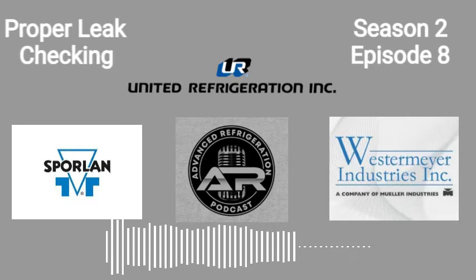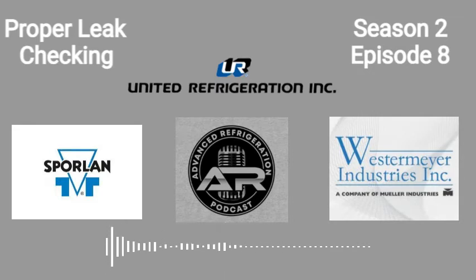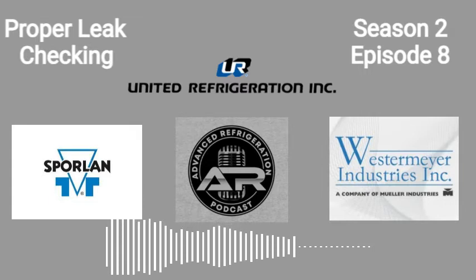If it's a three set lineup where you have three separate cases, each separated from the next case, I'll just open all the doors and shut off all the fans and go in there and find it that way. Usually with the H10, I'll open all the doors up and turn it down, and usually can find it that way. I don't usually turn the fans off unless I absolutely have to.